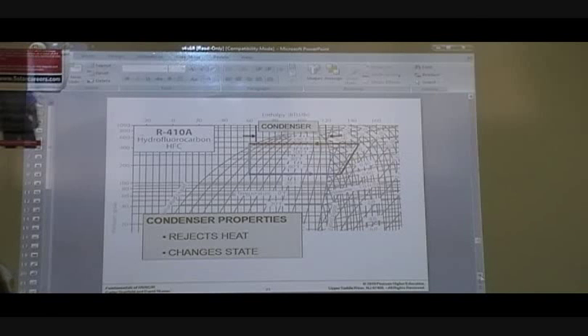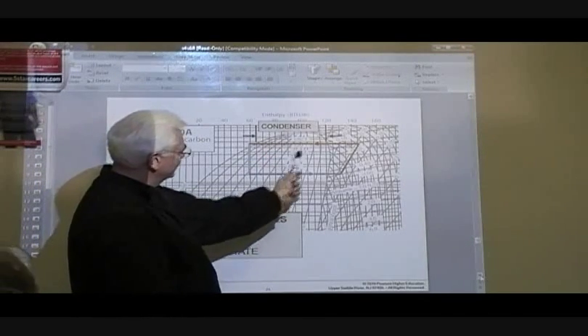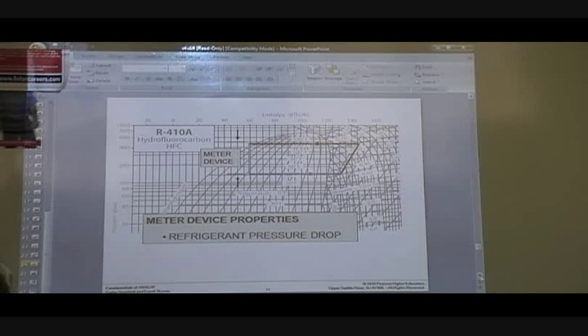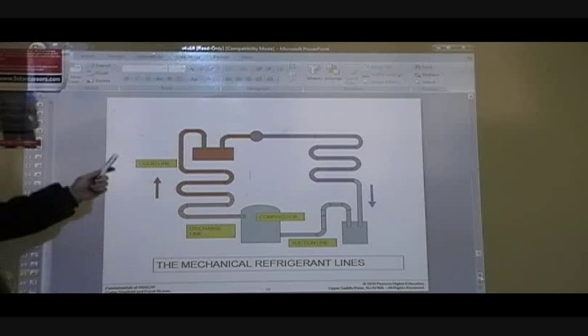And that's what happens in your condenser. Again, look at that additional heat that was added. This is the heat that was rejected from the conditioned space. This heat here is from the heat of compression and heat from the compressor motor. Metering device, that's where the refrigerant enters a metering device. And if you notice pressure changes, temperature changes, there's no input, no net refrigeration effect that occurs that can be measured. And again, you've got your refrigeration components. If you understand the basic vapor compression refrigeration cycle, you can understand the pressure-enthalpy diagram.